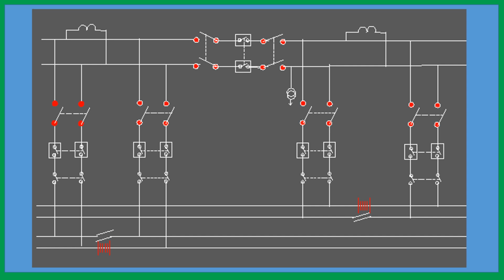Here the first two interrupters for sectioning and the last two interrupters for sectioning. Last two interrupters for upline and first two interrupters for downline. And for both the cases, auto transformer is compulsory here, because your return current will come to the auto transformer to the feeder. Feeder is the return current path, but without auto transformer, you connect it in the track and then it will return to the feeder. Okay. So this is the system of 2 into 25 kV.